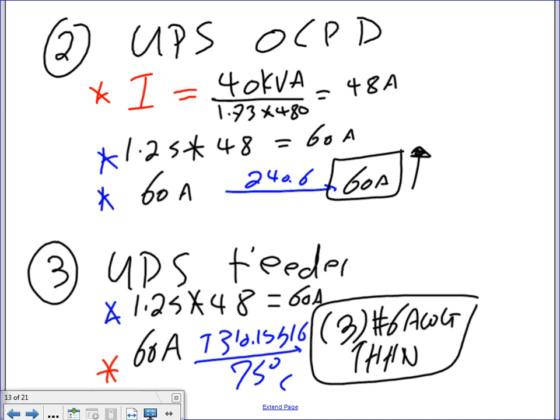Now, Derek, why 3 conductors? Typically, for UPS, we don't need a neutral. So what we do is we send 3 phases to this system. It's a 3-phase system only. Number 6. Remember to go to the 75-degree column. Everything is 3-phase, rated for 75-degree lugs and what not.